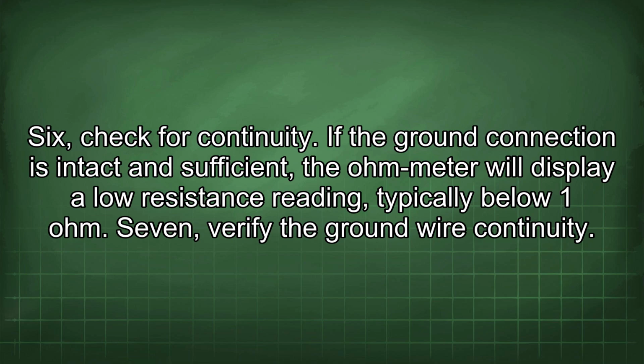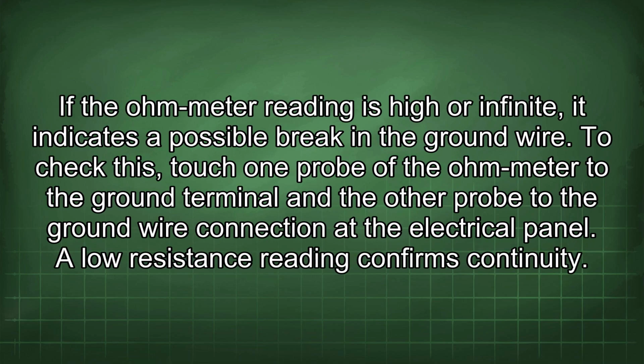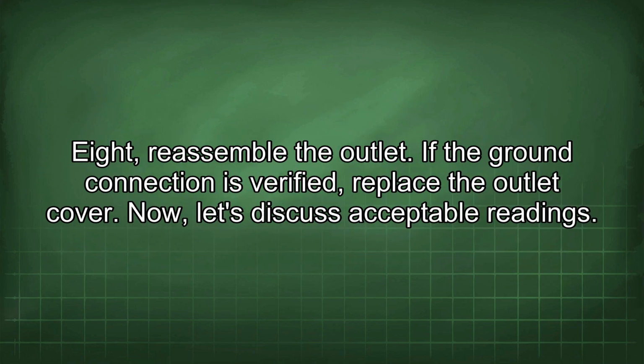7. Verify the ground wire continuity. If the Ohm-Meter reading is high or infinite, it indicates a possible break in the ground wire. To check this, touch one probe of the Ohm-Meter to the ground terminal and the other probe to the ground wire connection at the electrical panel. A low resistance reading confirms continuity. 8. Reassemble the outlet. If the ground connection is verified, replace the outlet cover.